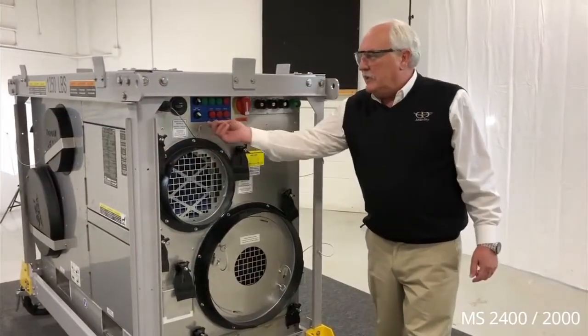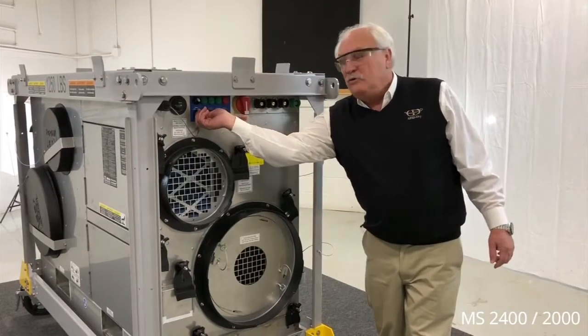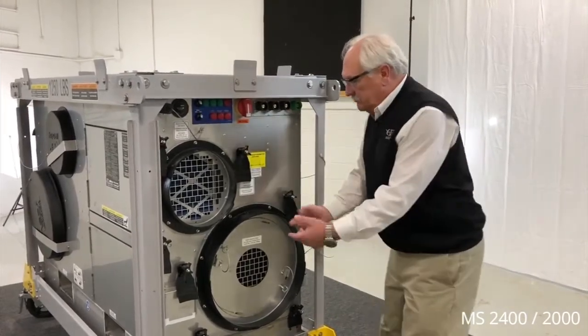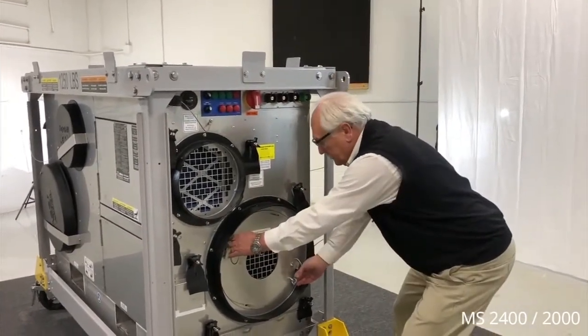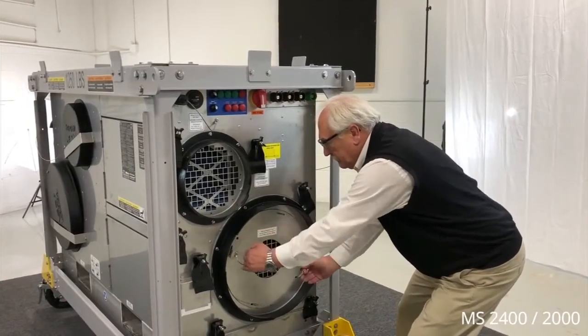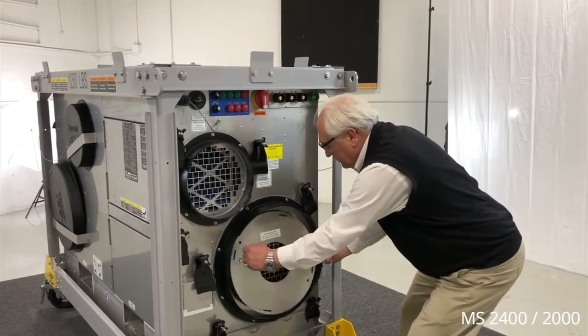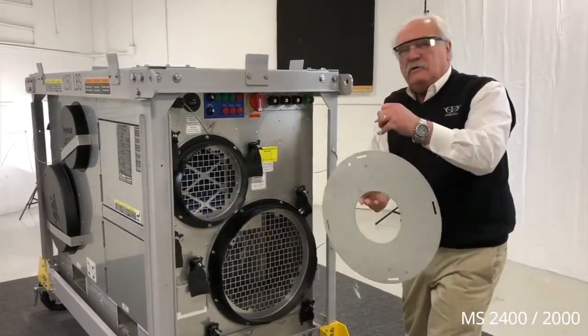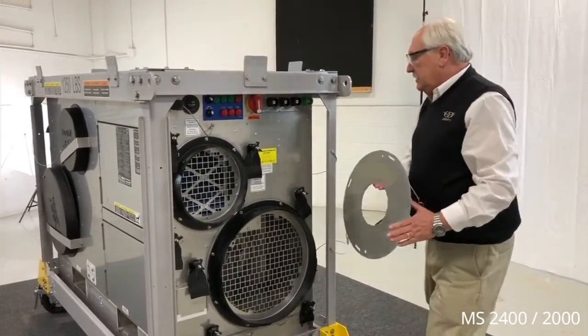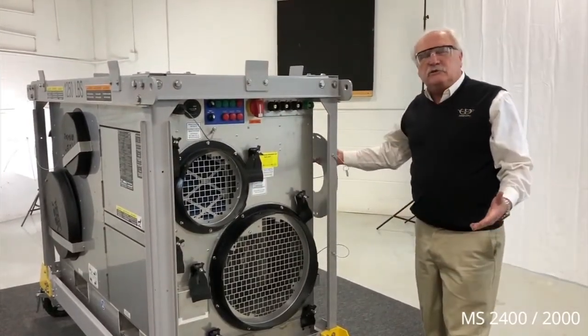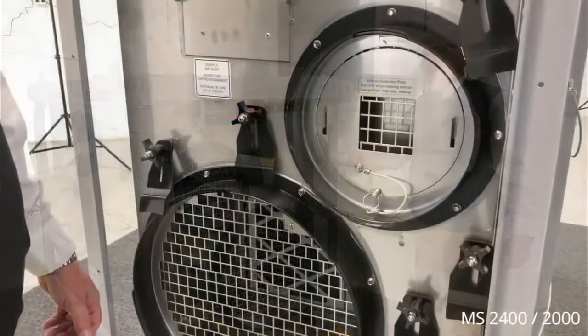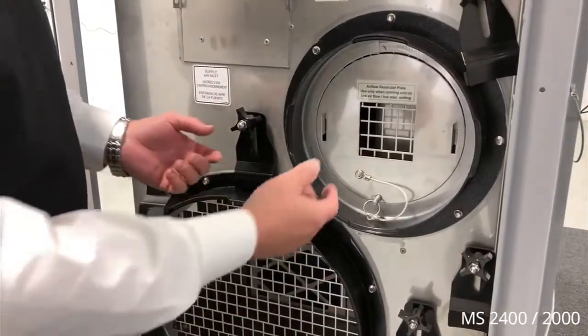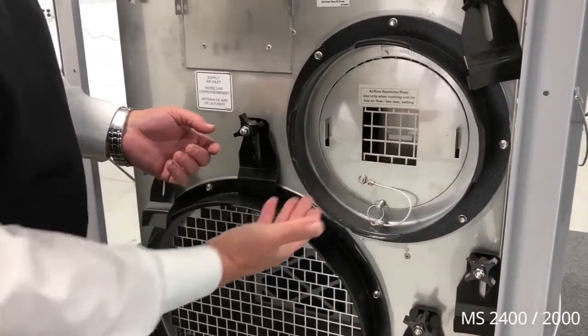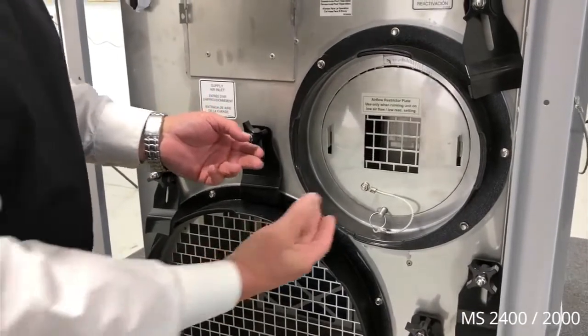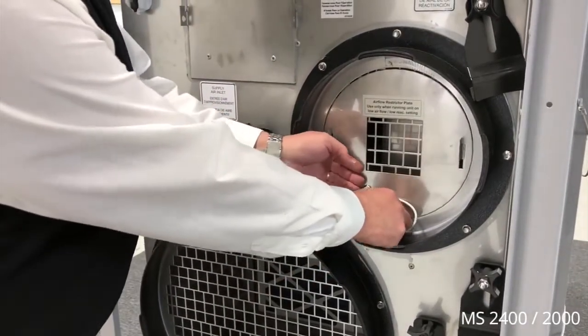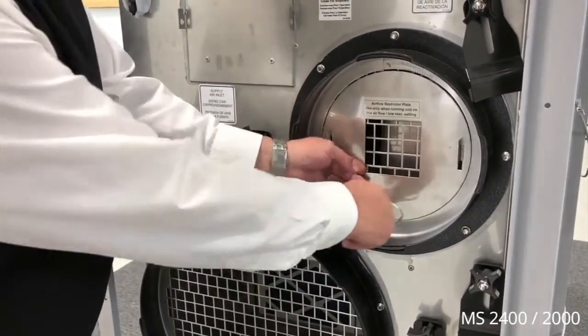To operate in the high setting, the selector switch should be moved to high, and the restrictor plate can be removed by simply removing the 2 pins, rotating the plate, and removing it. There's also a set of pins located on the side of the unit to store the restrictor plate. For high-speed operation, the restrictor plate on the reactivation airstream must also be removed to allow the proper reactivation airflow.